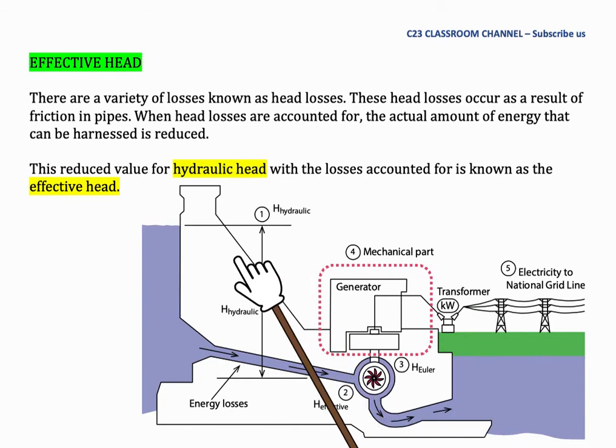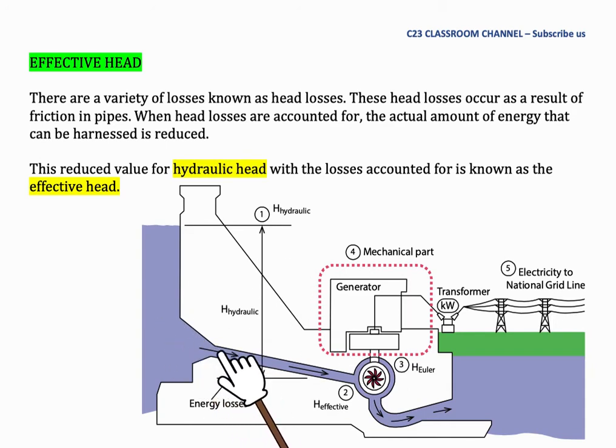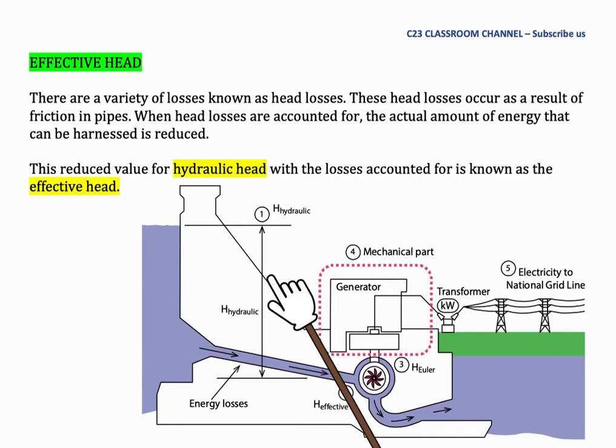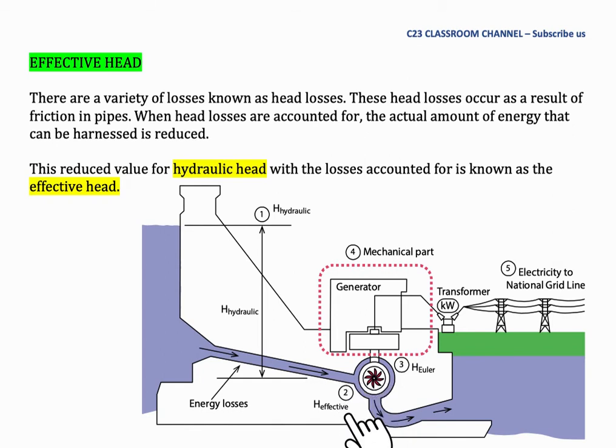From this diagram, we could understand that water from this dam will have potential energy by this height. This water will flow to the Francis turbine in a pipe system. As we learned previously, in a pipe system like this, there are losses due to friction. We need to deduct the hydraulic head with the energy losses along the pipe. The net head that occurs at the Francis turbine inlet is called the effective head — it is the effective head that becomes the input for the Francis turbine.